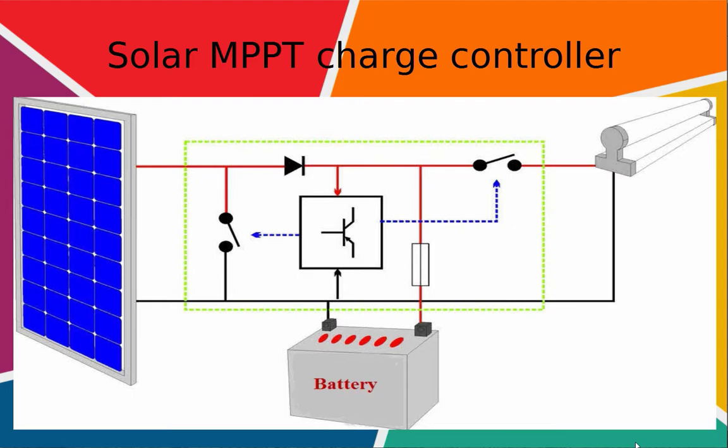Most modern MPPTs are around 93 to 97% efficient in the conversion. You typically get a 20 to 45% power gain in winter and 10 to 15% in summer. Actual gain can vary widely depending on weather, temperature, battery state of charge, and other factors.